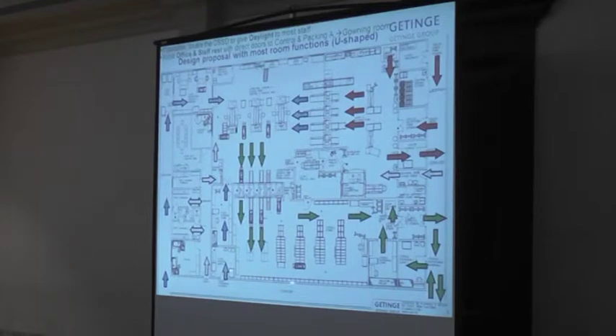Here we have a clean material. That is something that sometimes is forgotten when I see designs. So we need clean material to go into the packing area to be packed together with the instrument. We might have cotton balls, we need paper to wrap the tray. So we take in clean material here. Through what? Windows? Through a door. We use a door here, and then there is a window, and there is a conveyor belt. I will show a closer look at that very soon.